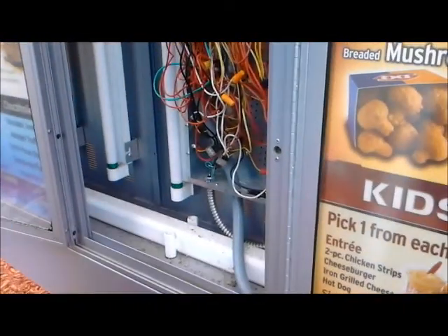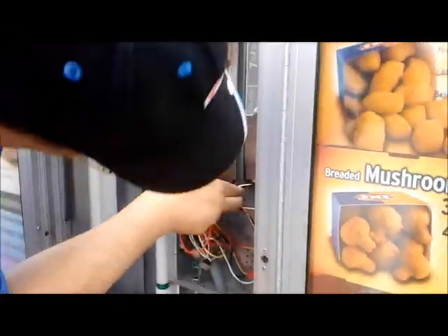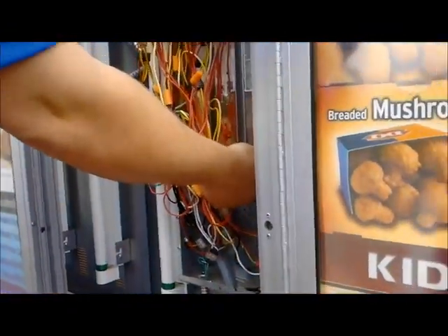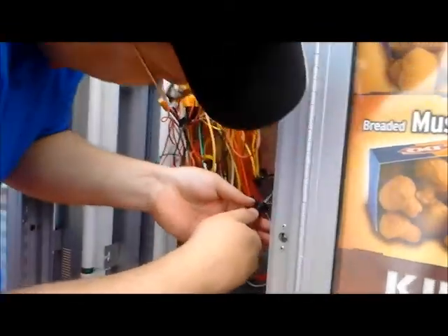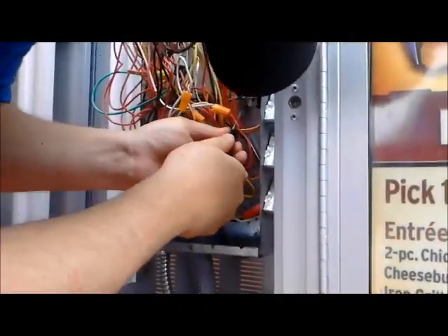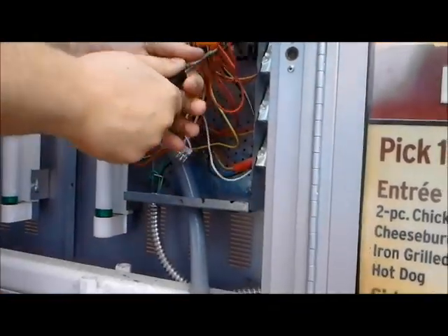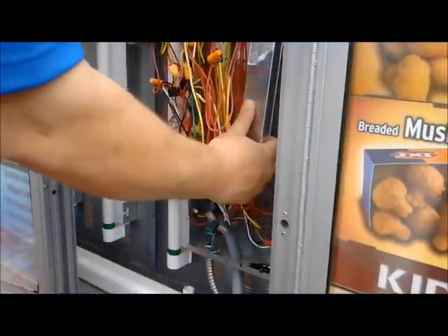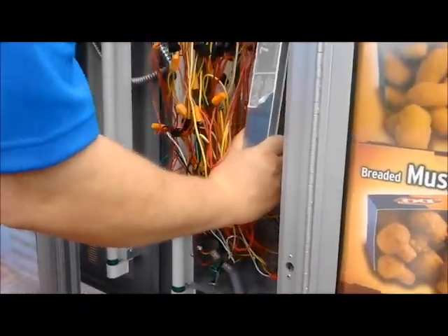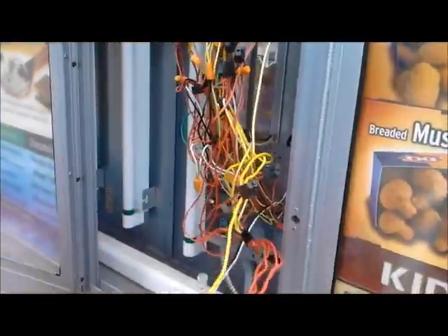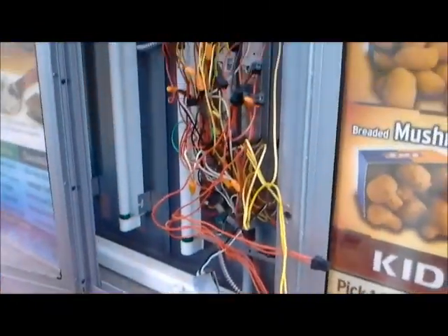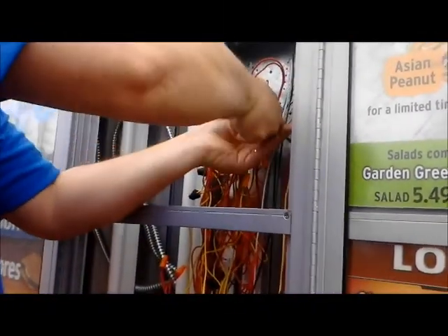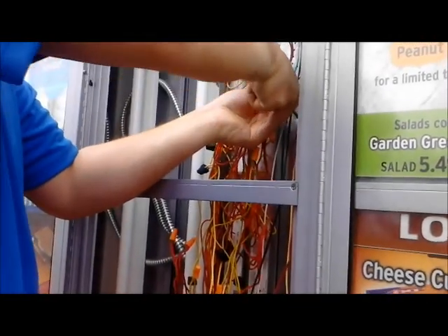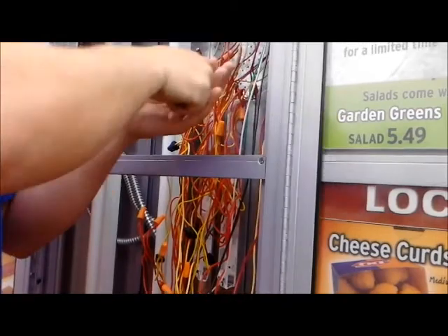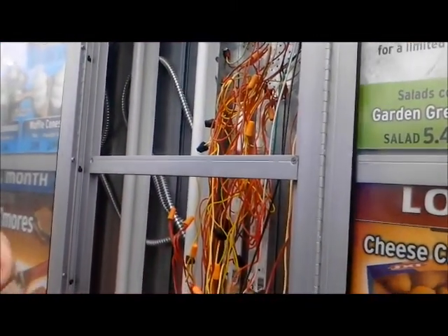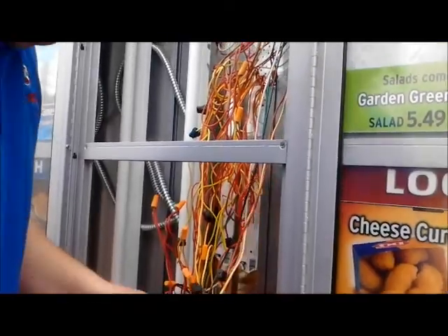Okay, we're going to leave that bolt down there, and as you can see, this black gunk here also caused the ballast to stick to the plate there, which isn't good. And since we just loosened the top one up, we're just going to pull the ballast out like this. All right. And we're going to loosen this bolt up a little bit so we can slide the new ballast in reasonably without a lot of issues. But I think we're just going to try and slide it in as is, since it's a lot more hassle to pull that one out than it's worth.